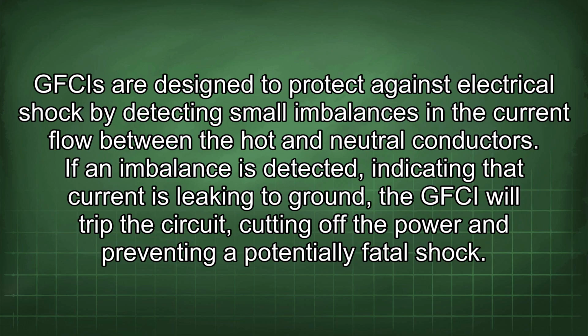GFCIs are designed to protect against electrical shock by detecting small imbalances in the current flow between the hot and neutral conductors. If an imbalance is detected, indicating that current is leaking to ground, the GFCI will trip the circuit, cutting off the power and preventing a potentially fatal shock.